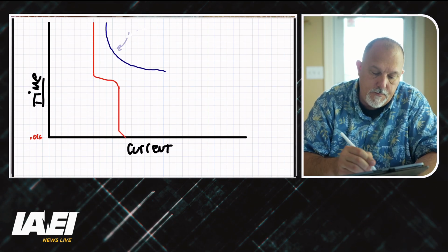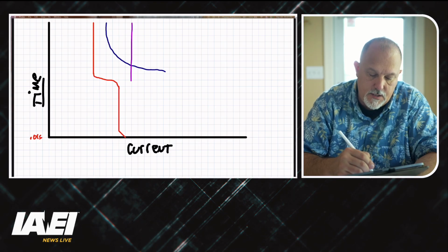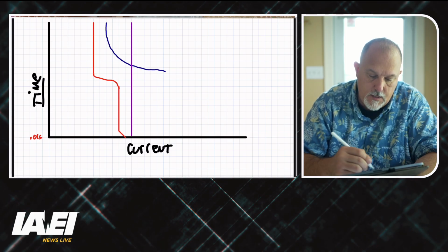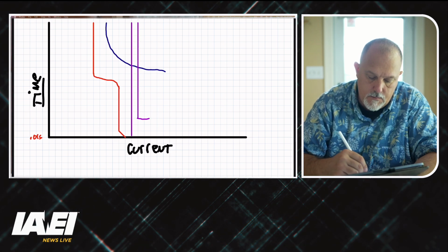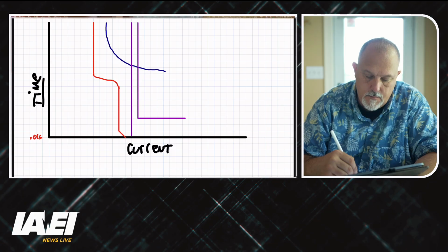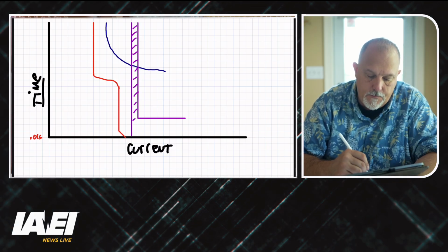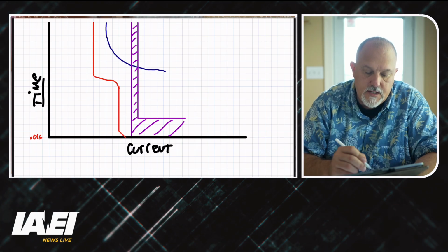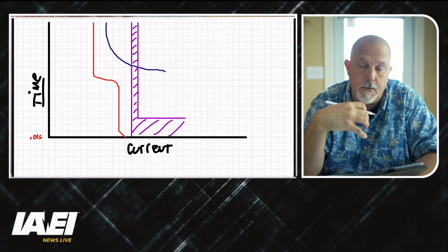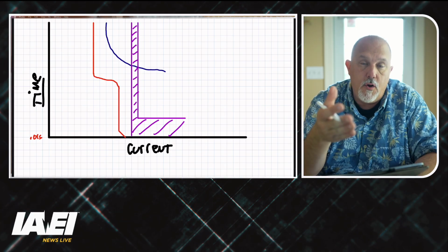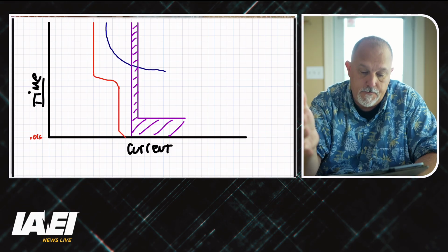If she did an instantaneous trip only device, it might look something like this. Right? So this would be your instantaneous only in between, and the fact that you have an instantaneous only breaker and the overload, which is separate. Now you've provided both levels of protection.